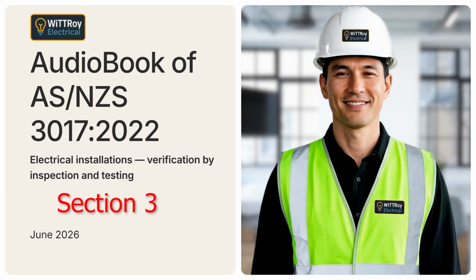Isolating devices must be checked. This includes main switches. Connecting devices must be checked. Examples include neutral bars, earth bars, and active links. The connection and fixing of wiring and switchgear must be checked. Identification and labeling of electrical equipment must be checked. Protection against external influences must be checked. The construction of the switchboard should be checked against the applicable standards. The correct RCDs must also be checked, or the correct alternative protection method where allowed.